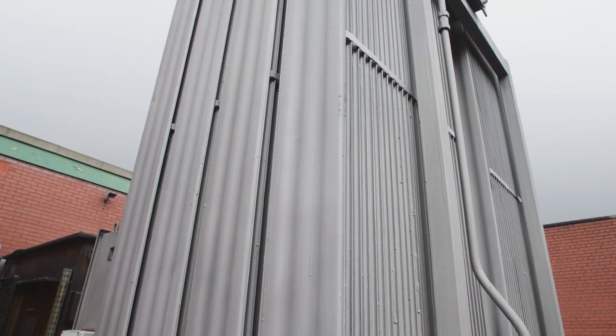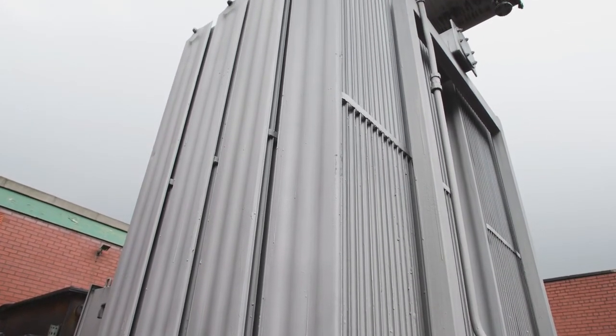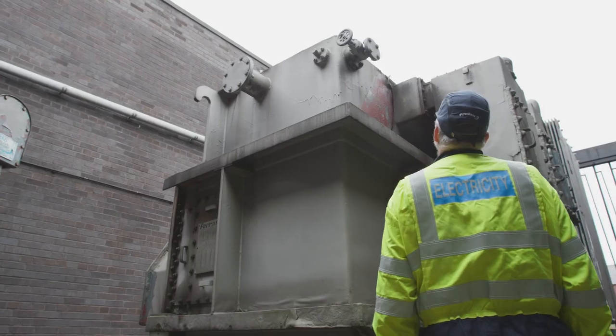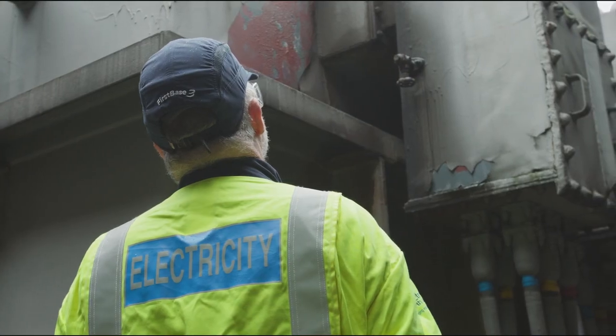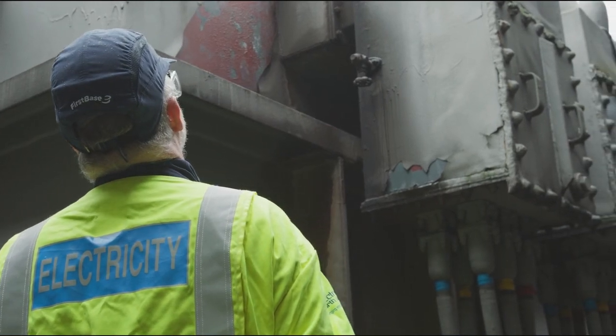The primary focus of the dissolved gas analysis and the tap changer monitoring system is to support the research and development of the oil regeneration of a transformer to maximise its life expectancy, while also understanding what effect this extension of life on the transformer has on the tap changer also. In addition, these systems also provide real-time health indices of the transformer and tap changer they are monitoring within their operating environment. Any changes in environment or deterioration of the transformer or tap changer is picked up immediately and investigated before any potential damage or deterioration is caused to the asset. This high level of monitoring on the transformer and tap changer assets will help optimise maintenance procedures and asset replacement strategies going forward within the organisation.